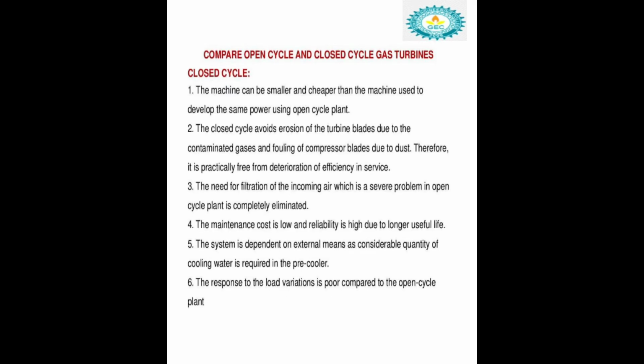Now the comparison between open and closed cycle. In the closed cycle gas turbine, the need for filtration of the incoming air, which is a severe problem in an open cycle plant, is completely eliminated. The maintenance cost is low and reliability is high due to longer useful life. The response to load variation is poor compared to the open cycle plant. These are the main differences between open cycle and closed cycle gas turbines.